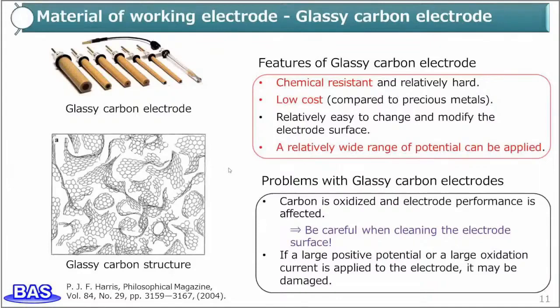The points to note are as follows: carbon can be oxidized and electrode performance can be degraded, so care must be taken when cleaning the electrode surface. Also, note that if a large positive potential, a large oxidation current, is applied, the electrode surface may be damaged.